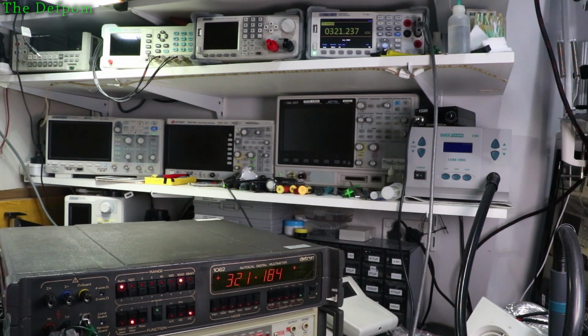300, this thing doesn't work properly. The Fluke at the 300 volt scale doesn't work. I don't know what's going on there. Is it anything below 340, I think it was, doesn't work properly. Yeah, 341's off, so 350 is okay. Between 300 and 350 doesn't work on that Fluke down there, so I need to fix that one day. But at least I know those particular ranges are problems, so 350, as you can see, is fine. And they pretty much agree. So 400, they agree. 500, they agree.